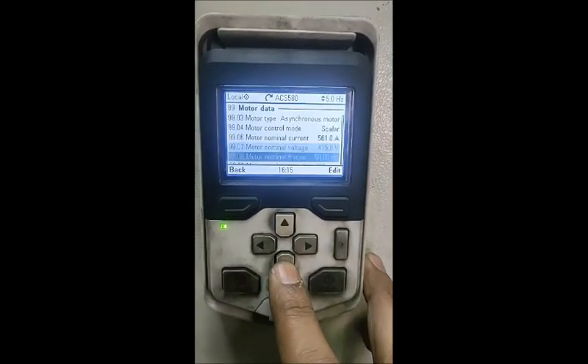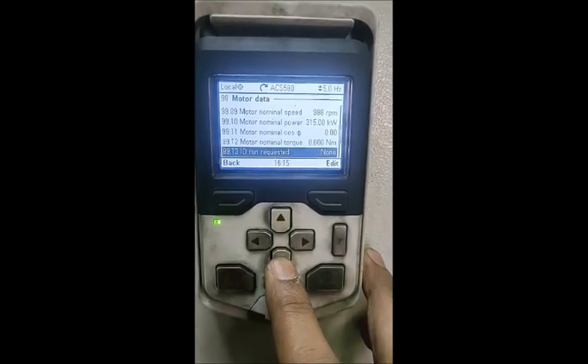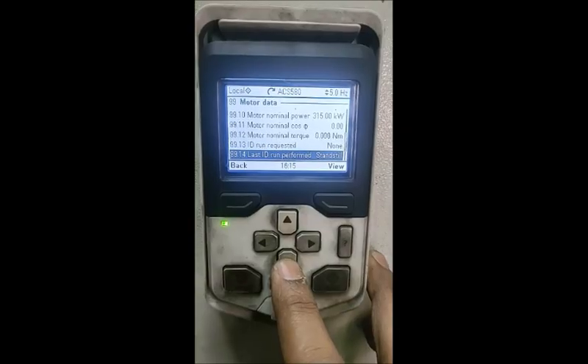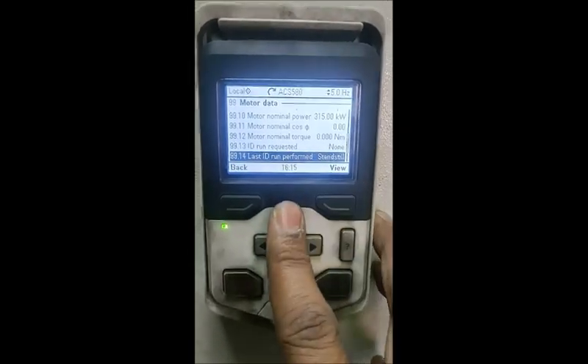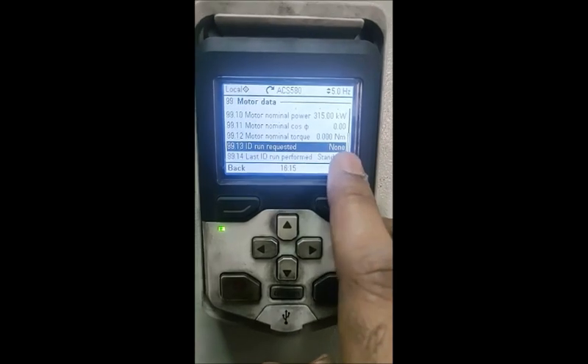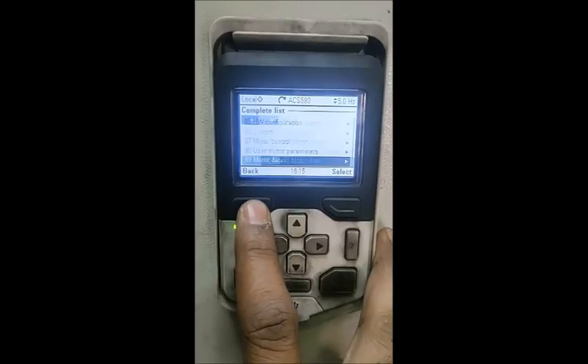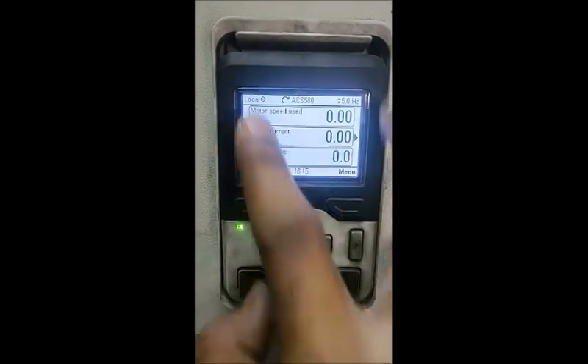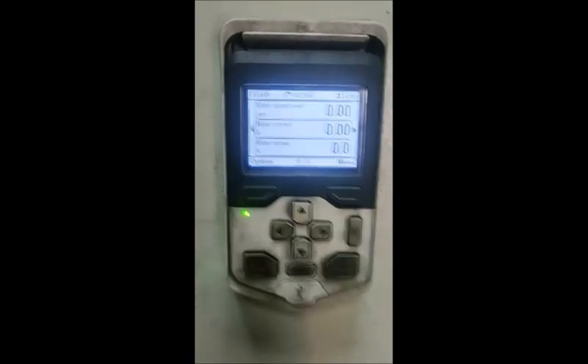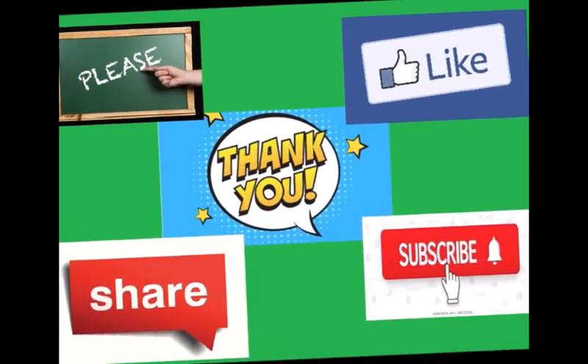The current you can see is 561. And see 'ID run requested' — by default it will come back to none. Earlier it was standstill, which we had selected, and 'last ID run performed' shows standstill. So we have checked all the parameters. We will come to the main screen once again — it is in local. We can bring it back to remote. Thank you for watching, guys — please like and subscribe.